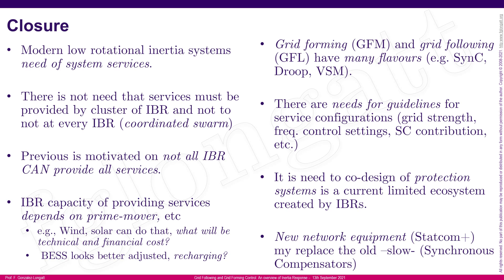Protection systems must be rethought. Grid forming control can replicate synchronous machine dynamics, but has limitations: short-circuit contribution, negative-sequence contribution, and zero-sequence behavior differ. Traditional overcurrent protection systems cannot be directly applied. There are published papers on negative-sequence behavior of inverter-based converters. New network equipment such as STATCOM+ is promising and may successfully substitute synchronous compensators in the grid.